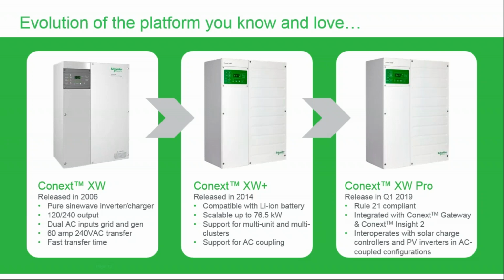electrical panels. It had dual inputs, one for generator and one for grid. It had a 60 amp 240 volt transfer switch, and it had an 8 millisecond transfer time. The other thing that didn't get fit into this slide was that it had power factor corrected charging, so it wasn't nearly as noisy electrically as the old phase control chargers. Then we went to the XW in 2014.